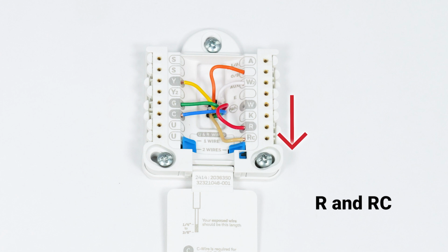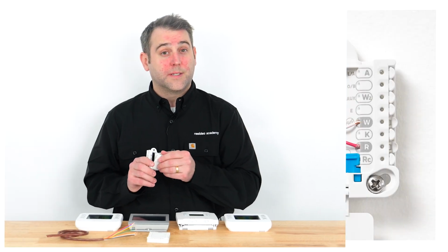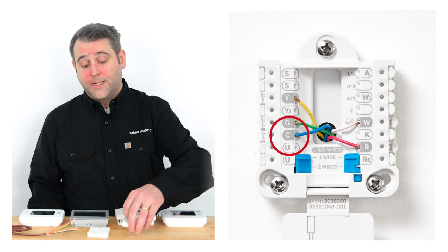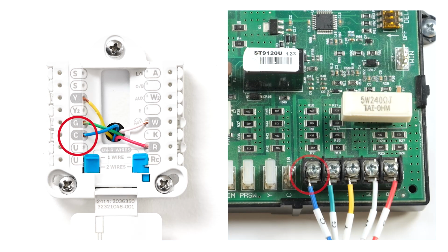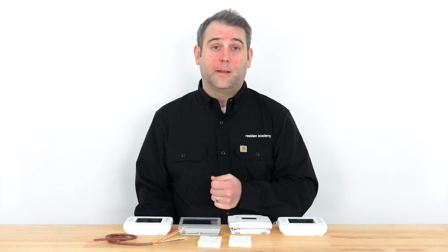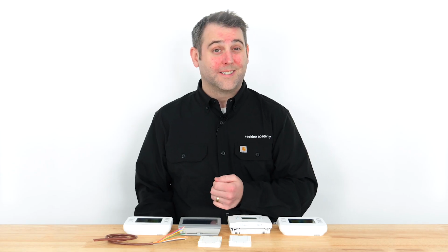If you have 2 wires, put them in the corresponding terminals. If you're installing a thermostat that uses a C wire, and your previous thermostat did not use a C wire, you may need to confirm that the C wire is connected both at the thermostat and at the HVAC system. We highly recommend contacting an HVAC professional to complete this step.